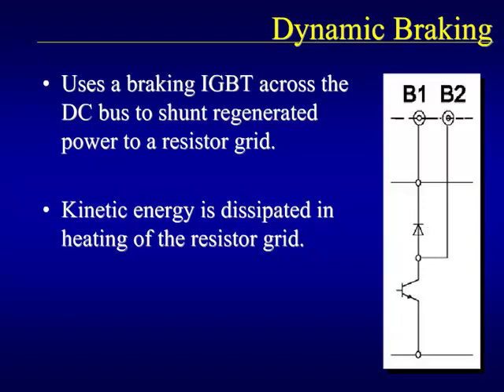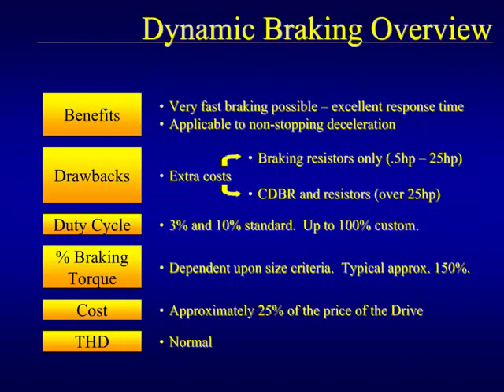Dynamic braking allows the motor to regenerate power back to the drive. As the DC bus voltage rises, a transistor turns on allowing additional DC bus power to be dissipated onto a resistor grid. Dynamic braking is an excellent method because of the available braking times and because it applies to deceleration as well as complete stops. Duty cycles and braking torques can be determined by the user. The major drawback is added cost — on smaller units, only resistors are required, but on larger units, both resistors and braking transistor units are required. This additional cost can be up to 25% of the drive price.